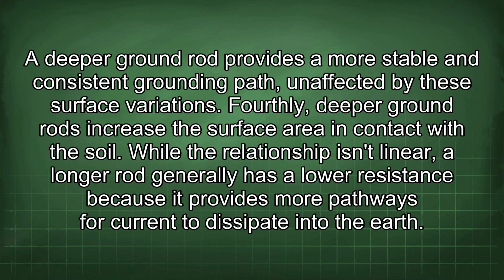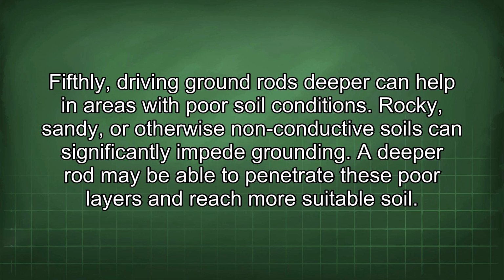Fourthly, deeper ground rods increase the surface area in contact with the soil. While the relationship isn't linear, a longer rod generally has a lower resistance because it provides more pathways for current to dissipate into the earth. Fifthly, driving ground rods deeper can help in areas with poor soil conditions. Rocky, sandy, or otherwise non-conductive soils can significantly impede grounding. A deeper rod may be able to penetrate these poor layers and reach more suitable soil.